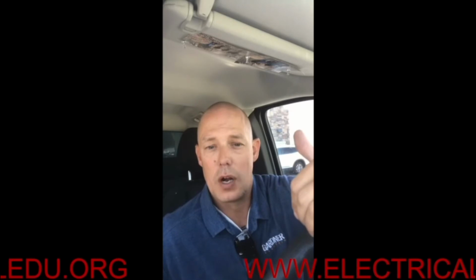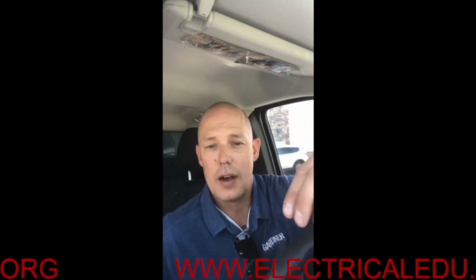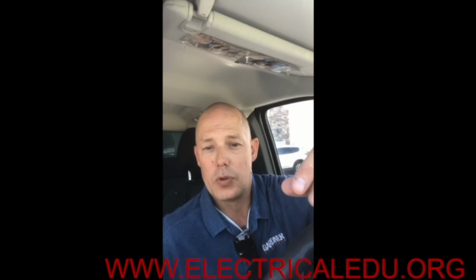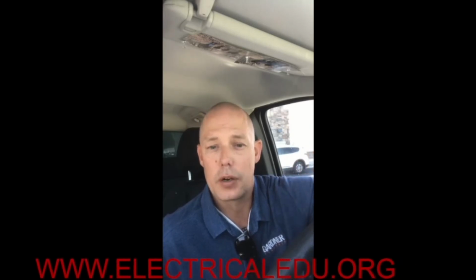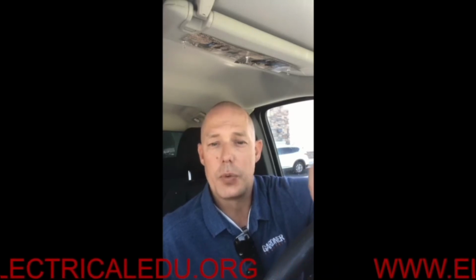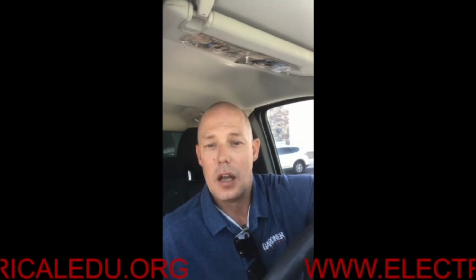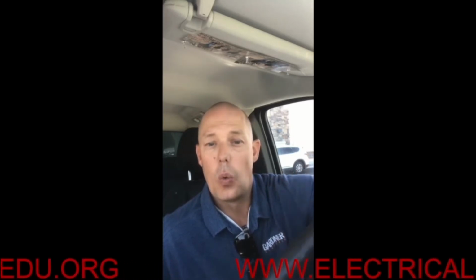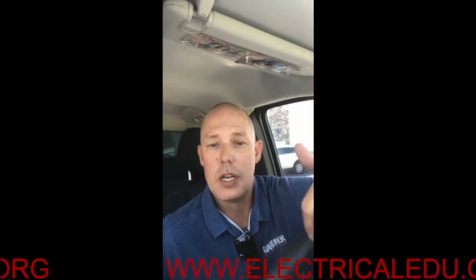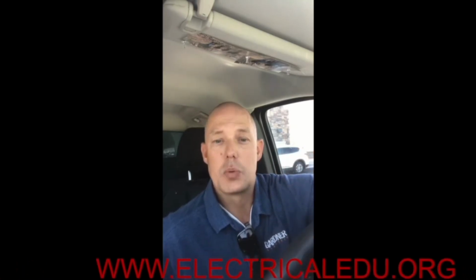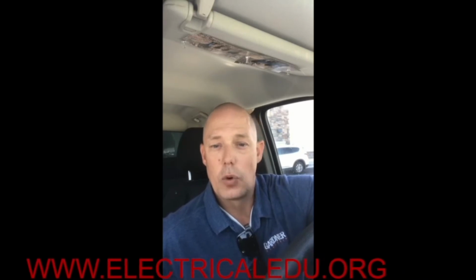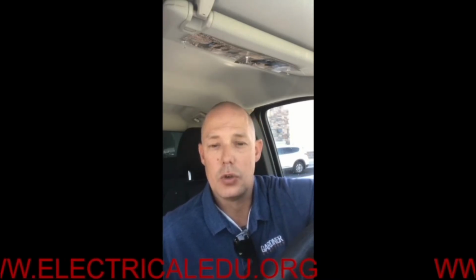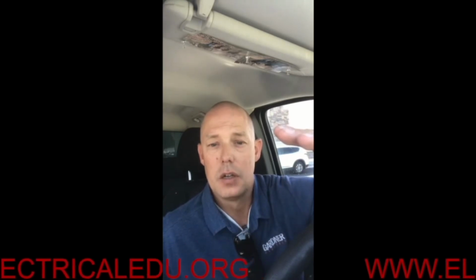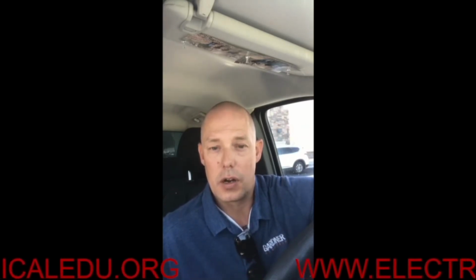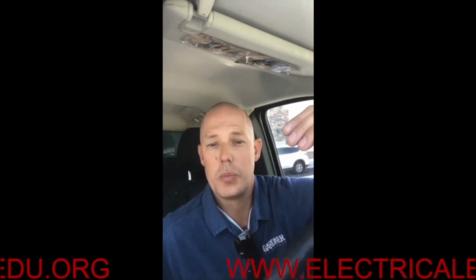So for this wire, if you saw on the nameplate that you have the 45 amp maximum fuse, you have to use that fuse or that breaker. But the wire size was 30 amps, so you would size your wire off of 310.16, and then the question comes in, what column do I use in 310.16? That's when you would go to 110.14(C). 110.14(C) tells you anything 100 amps or less is the 60-degree column. Anything over 100 amps is going to be the 75-degree column.